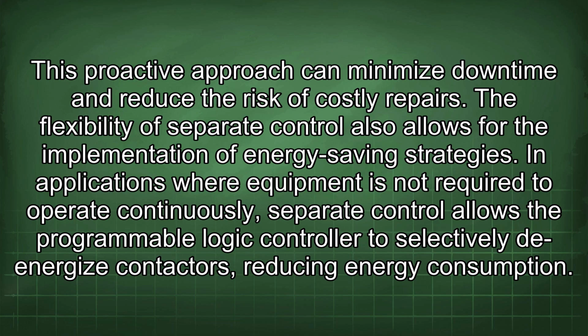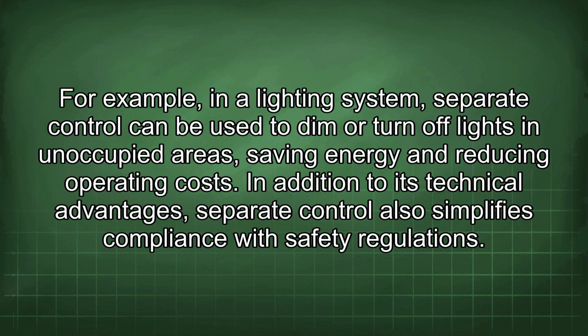The flexibility of separate control also allows for the implementation of energy-saving strategies. In applications where equipment is not required to operate continuously, separate control allows the programmable logic controller to selectively de-energize contactors, reducing energy consumption. For example, in a lighting system, separate control can be used to dim or turn off lights in unoccupied areas, saving energy and reducing operating costs.